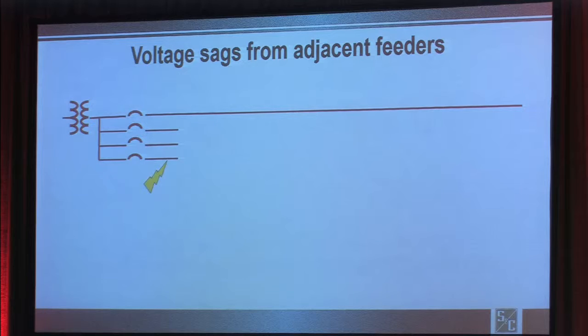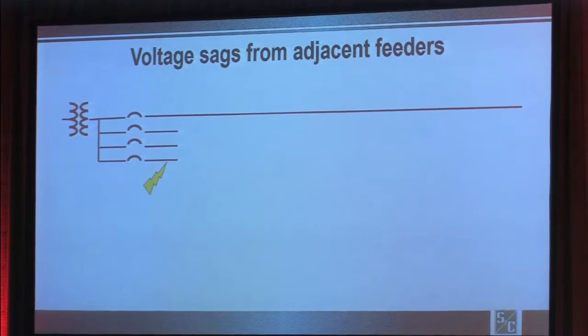And what happens is you'll have a fault on one of the feeders. All 4 feeders are connected to the same substation transformer. When you have the fault on the one feeder, if it's a big enough fault, it actually sags or dips the voltage on that feeder. And since it's connected, the other 3 feeders also see that same voltage sag. What FPL determined was somewhere around a 70% voltage sag, 70% of normal, so 100% normal down to 70%. Somewhere around there is where it starts to affect those electronic devices similar to what a momentary outage does.